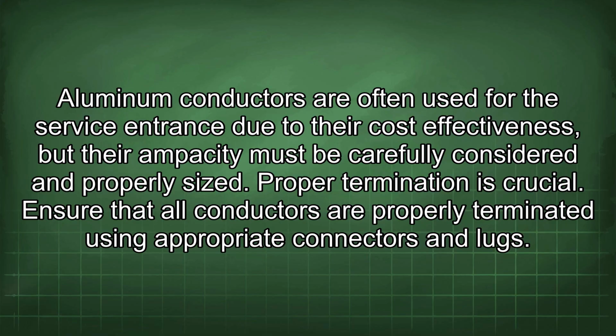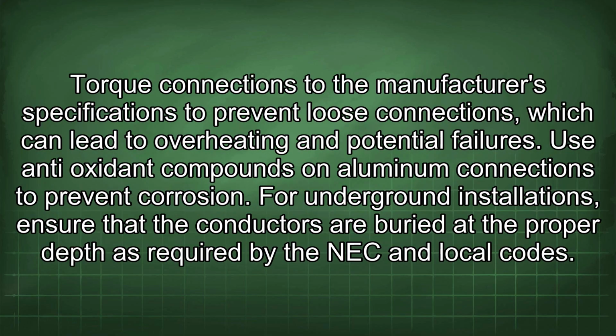considered and properly sized. Proper termination is crucial. Ensure that all conductors are properly terminated using appropriate connectors and lugs. Torque connections to the manufacturer's specifications to prevent loose connections, which can lead to overheating and potential failures. Use antioxidant compounds on aluminum connections to prevent corrosion.